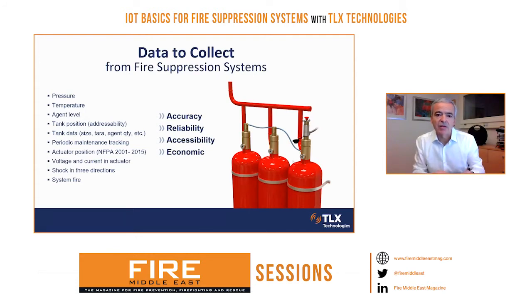For maintenance tracking, NFPA 2001 requests that the location of the actuator on the cylinder be monitored by the panel. So switches would be integrated into the actuator that tell us if the actuator is positioned correctly on the tank.